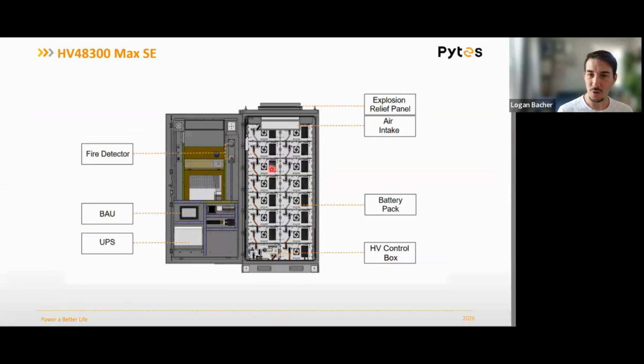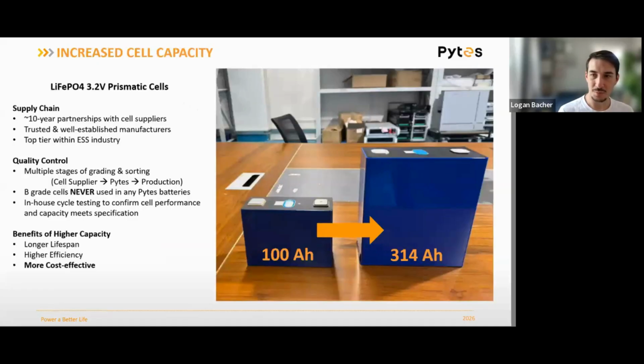But yeah, kind of the same thing going on inside. Like I said, fire detection, HVAC system, heat pump, aerosol fire suppression. That's all built in. This one actually does not have heating pads. Being that the modules are higher capacity, they're going to, I think, thermally regulate themselves a little bit better than the 100 amp hour model. So just keep that in mind. But again, the heat pump on the front can help control the temp in the cabinet.